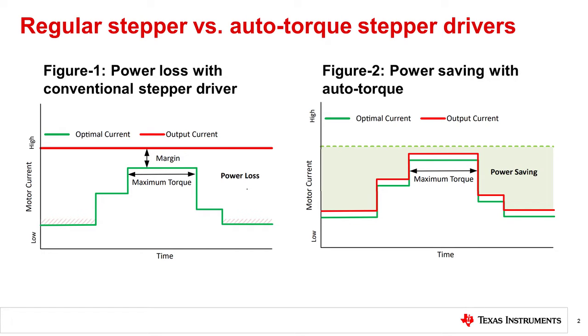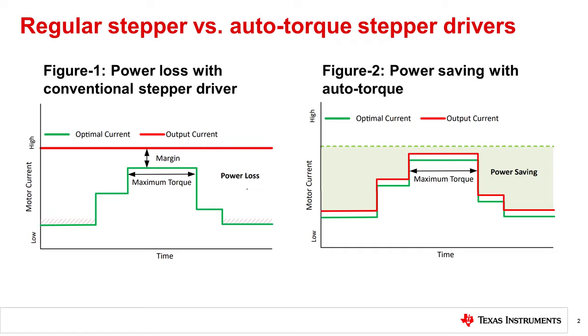In a typical stepper motor driver design, the motor current is set at a fixed full-scale current IFS, aimed at driving the maximum load torque expected in an application with some safety margin included. This is shown by the red line graph in Figure 1. This strategy works well from a power efficiency standpoint only if the load torque is constant and close to the expected maximum torque 100% of the time.